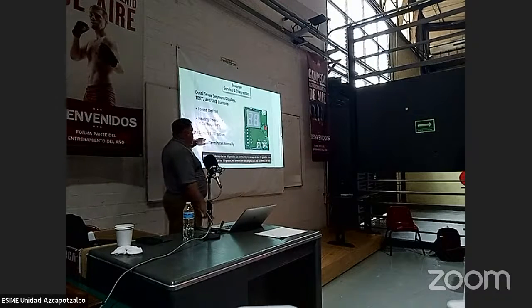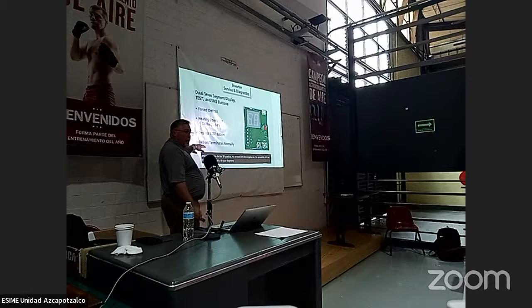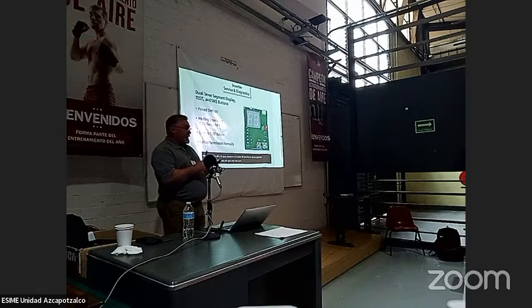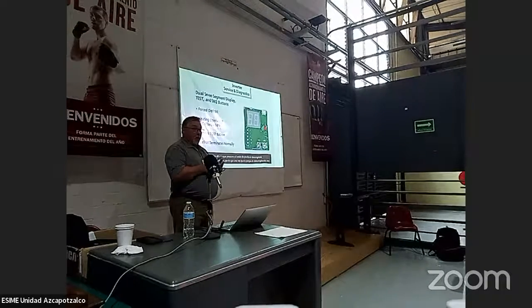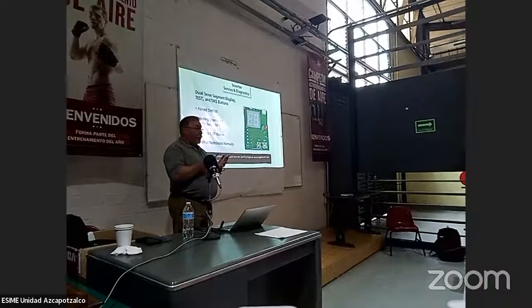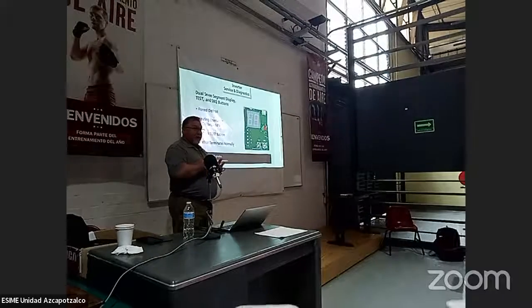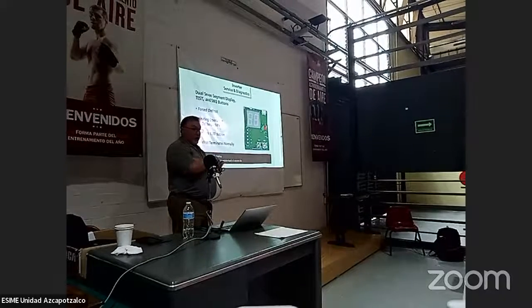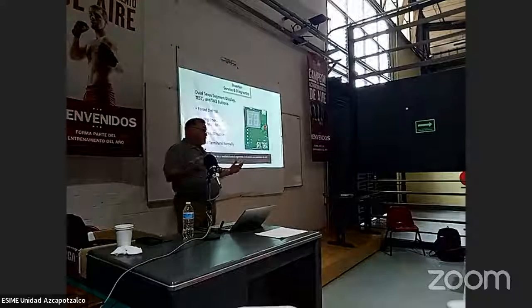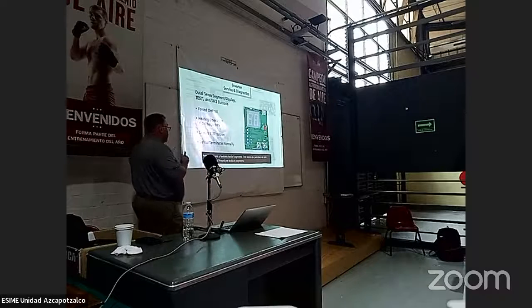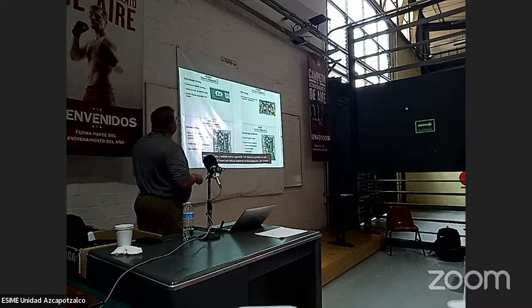When you press the test button, defrost will terminate normally. So once you put it into defrost, it's got to see the 60 degrees before it will initiate that, and it will also do the 6-minute oil return segment too. It'll go through an entire defrost segment.